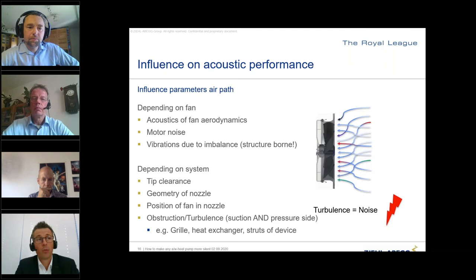What is one of the most important things when it comes to the operation of a fan is the simple equation that turbulence is noise. It's as simple as that. If you have any obstruction or turbulence on the suction side, especially, or at the pressure side, this makes for higher noises. This can be a grill, a heat exchanger, or any strut of the device.